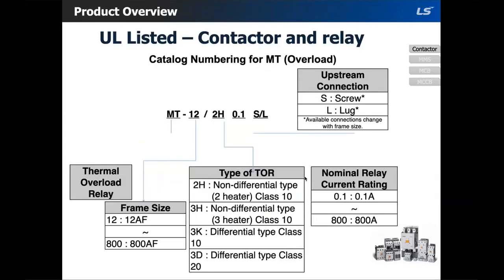Okay, just like the contactor, the catalog numbering system is also very simple. MT is the product code name, and the next would be your frame size. And then after that, you would choose the type of overload. So differential and non-differential. So the difference between those two is differential is considered to be a higher sensitivity relay as it has a phase failure detection. Whereas a non-differential doesn't have a phase failure detection.